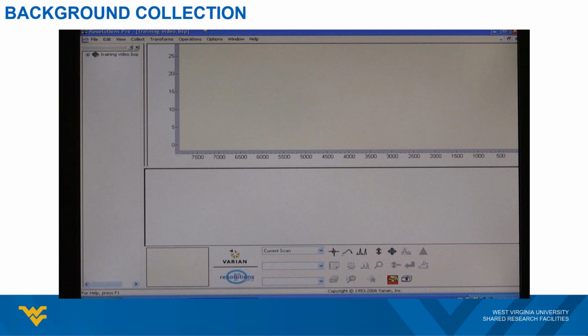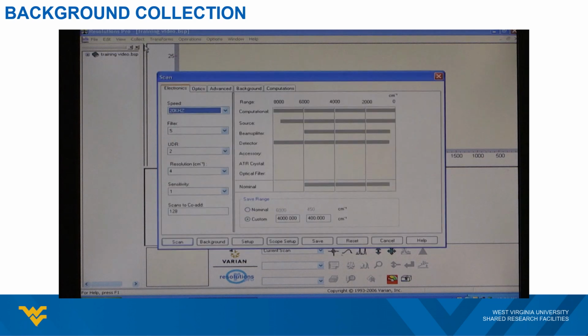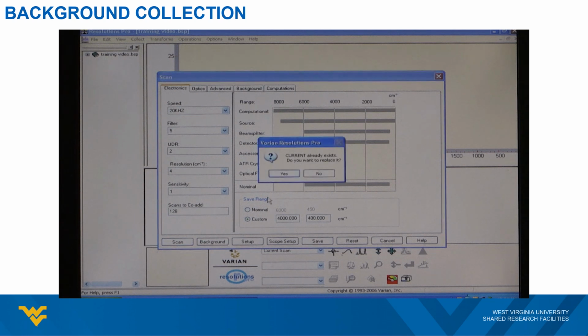The background measurement records all the absorption features present within the instrument and atmosphere, including components like water vapor and carbon dioxide. Later, the sample spectrum is compared with this background, providing an absorption spectrum that originated solely from the sample. To collect the background, leave the ATR sample tip open as suggested earlier. Then simply click the background button located at the bottom of the scan window. This will start a background measurement using the parameters previously selected.